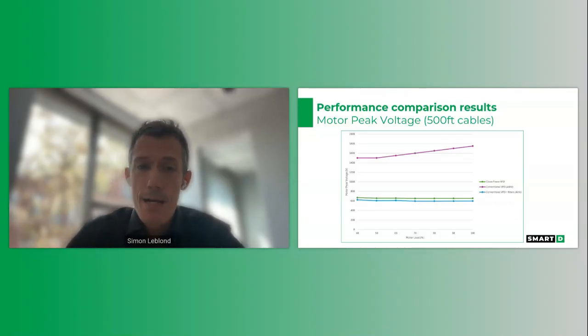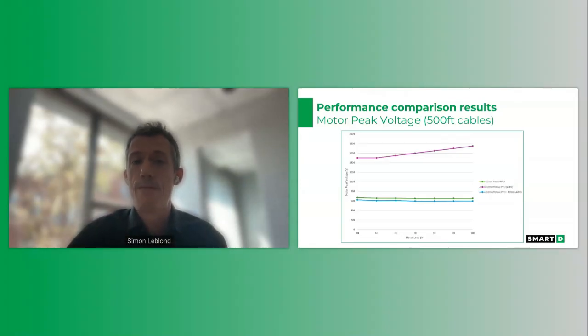You could ask, hey, there's a small difference between the Clean Power VFD and the sine wave filter. Indeed, the Clean Power VFD has an active front end, so it is able to compensate voltage drop, and this is why you're seeing that voltage a little bit higher. Actually, the active front end from the Clean Power VFD is capable of compensating that voltage drop up to 20%, giving the opportunity to have even longer cable without any issues.